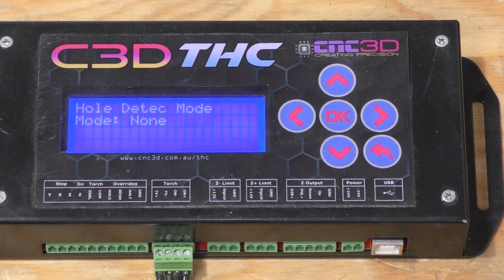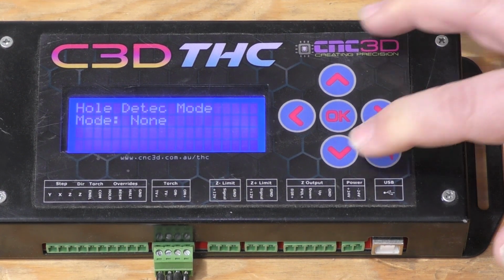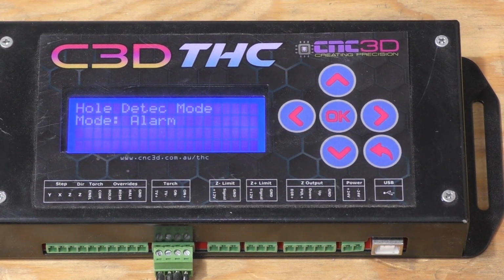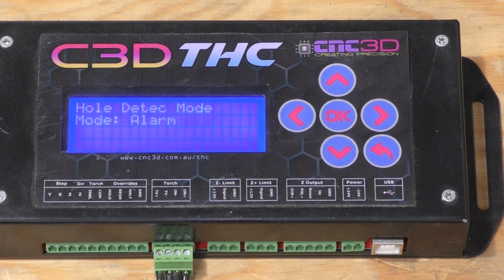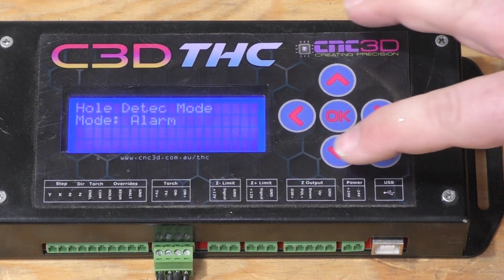You may run into an issue where it hits the other side of the material, or if you've gone over the edge of the stock, it will just continue plunging down until either the plasma torch turns off and you lose the arc OK signal, or you intervene and something else happens. If we scroll here, we've got another option, which is alarm. So hole detection mode alarm, if it travels over the hole or over the edge of the material, there is a delay, which we'll get to in just a minute. If it detects that it's still high voltage at this point, it will send an alarm signal or an e-stop signal to the controller to stop the job. So that will prevent your torch from crashing into anything else, but it will stop the job.